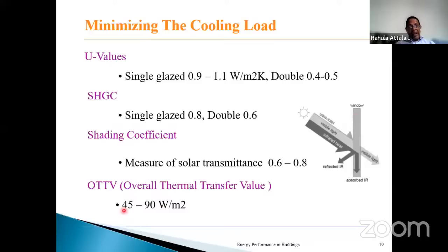And overall thermal transfer value is the overall value given to the composite, incorporating walls, windows, and so on. This value can be computed, and the standards will give how this can be calculated. Ideally, it should be in the range very close to 50 or so, but currently Sri Lanka uses values close to 90. So these values are obtained from the standards, and this diagram will indicate how the radiation coming from the sun is separated into different components by a glass.